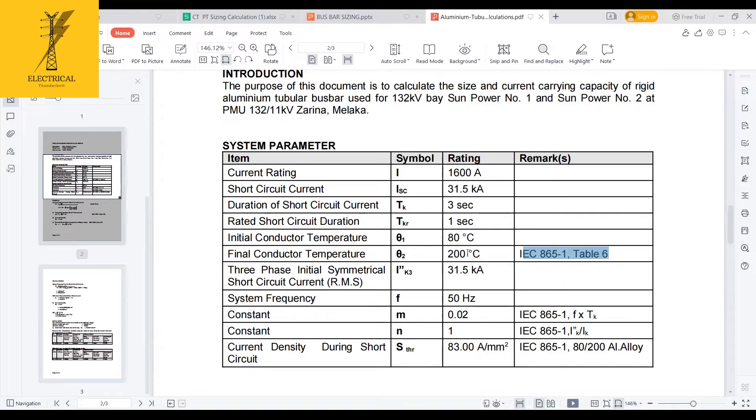And this, you already know, short circuit current. Frequency is 50 hertz. And the M and N, I am getting from IEC 865, from the graphs, what I have shown before in the presentation. And this is the current density during the short circuit current. This is for the aluminum alloy, as per IEC 865, which is 83 amperes per mm square.